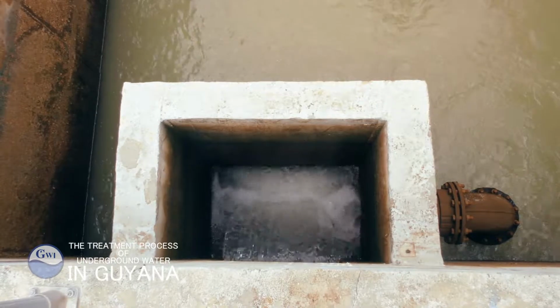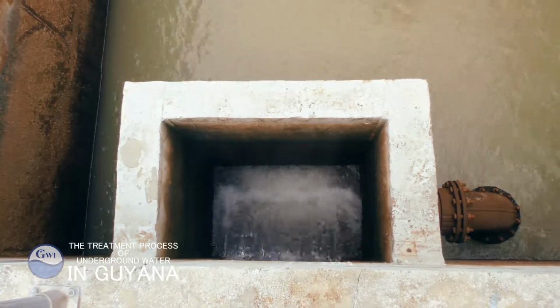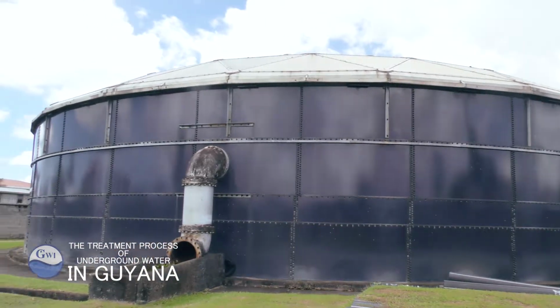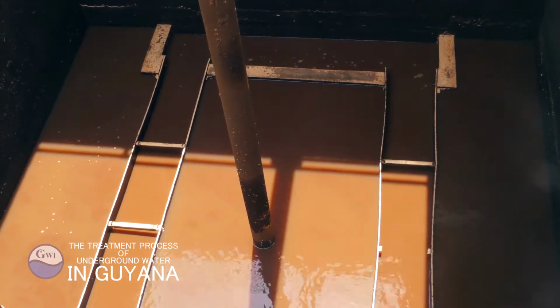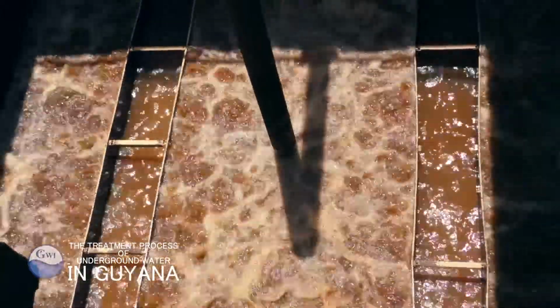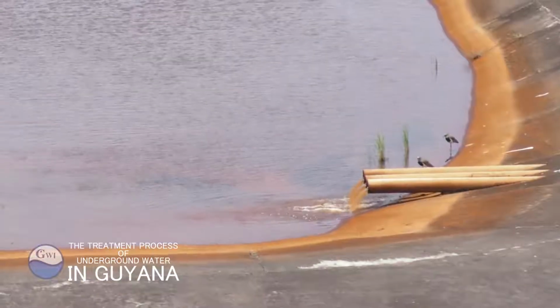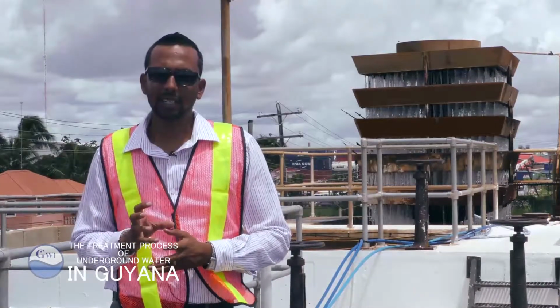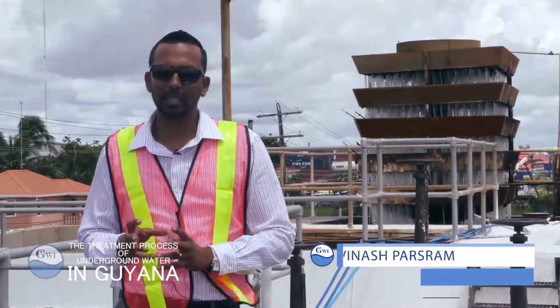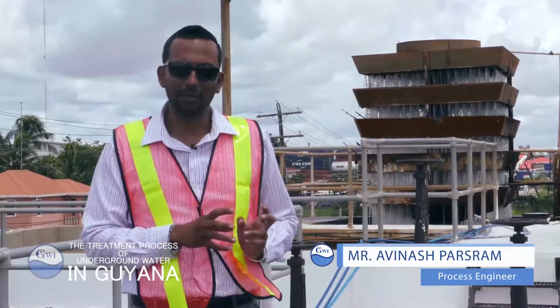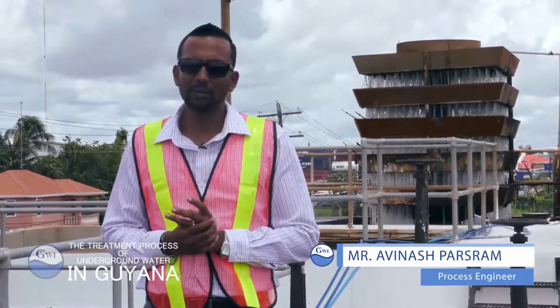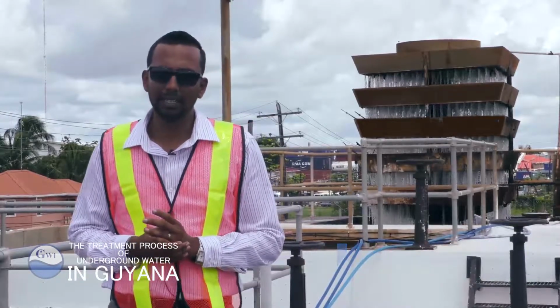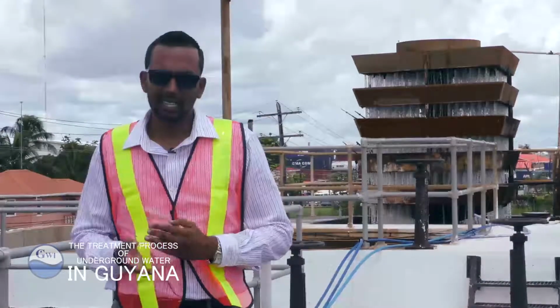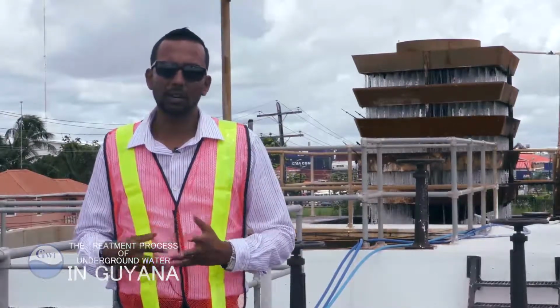The rapid sand gravity filters are packed with media that create a barrier to the passage of the iron precipitates, or groups of particles known as flocks, and disallow them from entering the storage reservoir. These filters are cleaned by a process known as backwashing, where water flows in the opposite direction to flush the accumulated iron in the filter media. Therefore, the iron content in the final water, that is after the treatment, is much lower than that from the aquifer. In the reservoir, chlorine is added to maintain a residual of about 0.5 milligrams per liter when it enters the distribution network. This caters for any contamination that may occur in the distribution network.